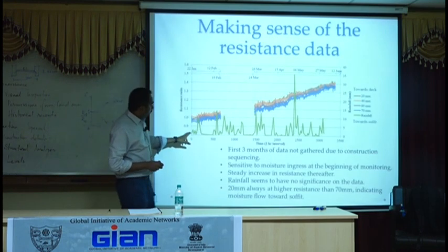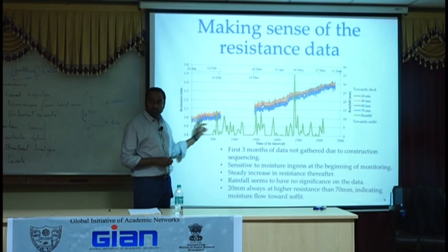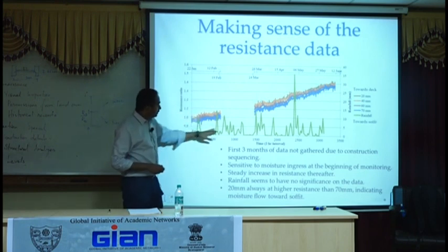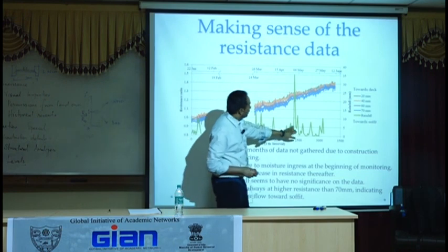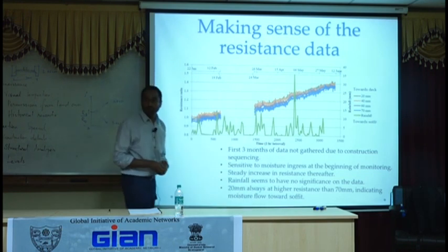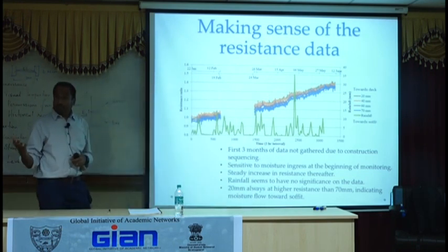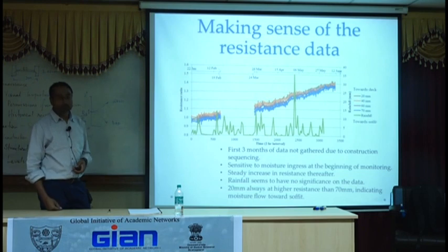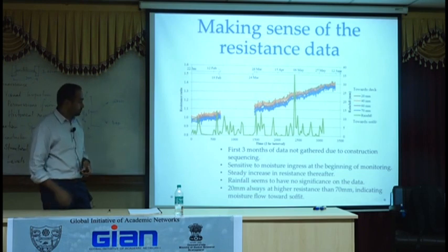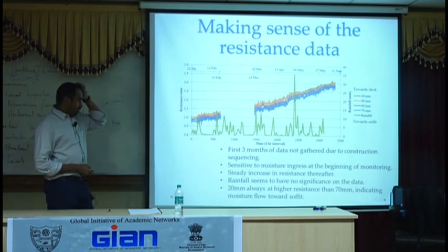And we also plotted the rain data to see would the rain data shift it. Okay? And these are the peaks of the rain data, and it doesn't seem to have any influence on resistance. That gives you confidence. That means it's not connected to rain, which means it's sealed from the environment.